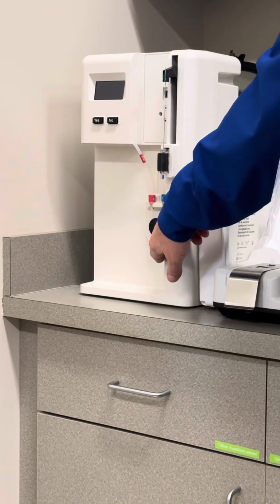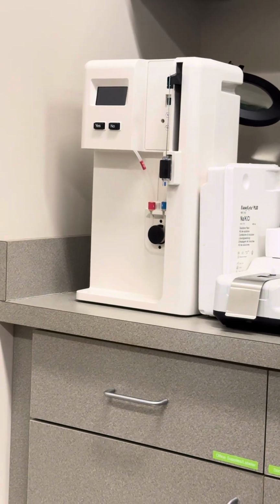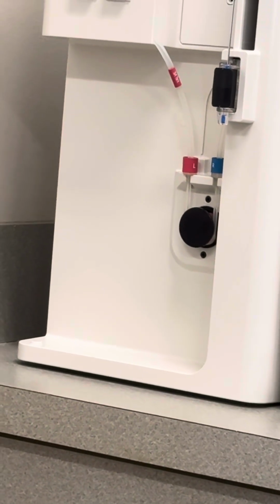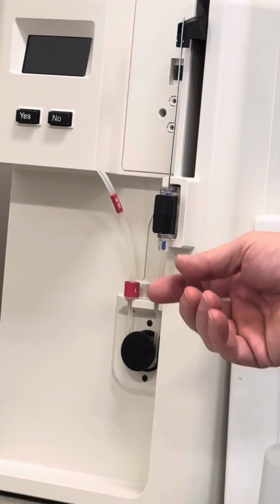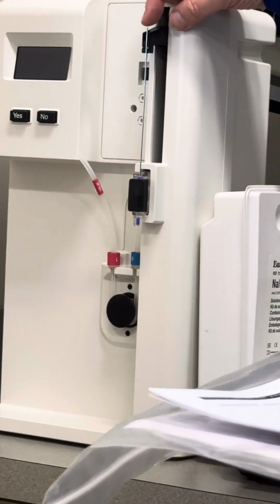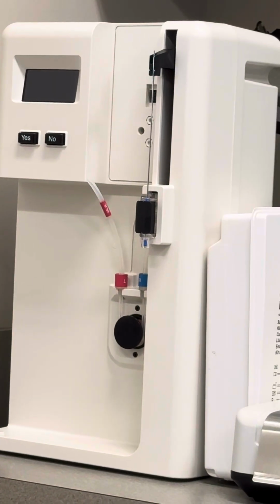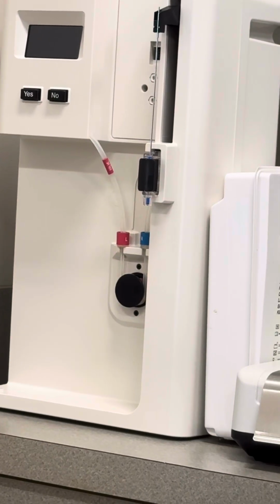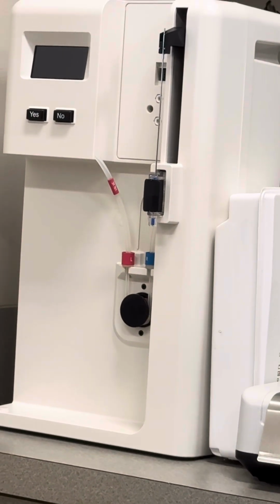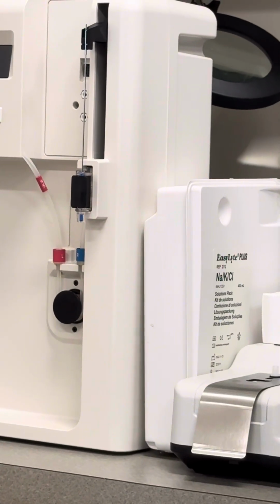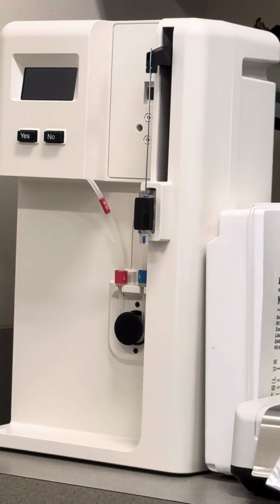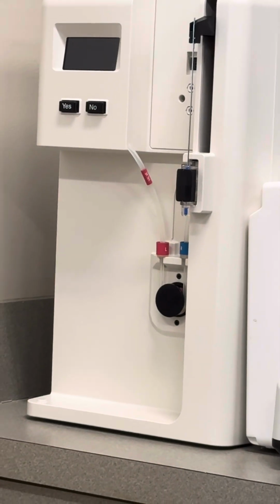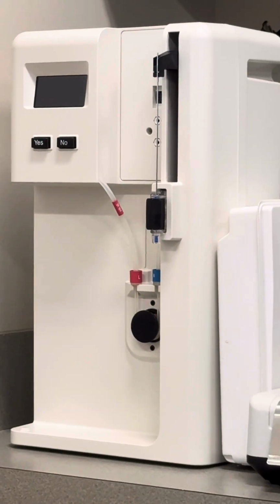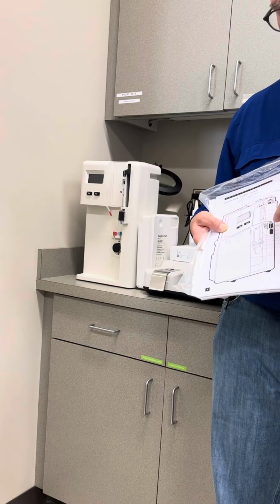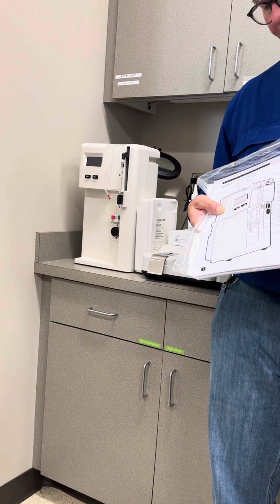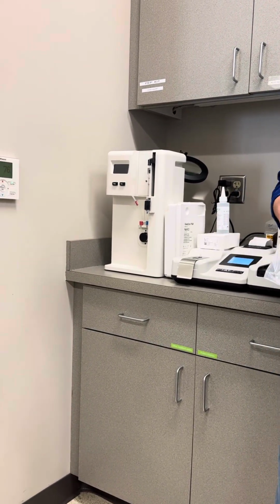Of course, you have your peristaltic pump and the tubing for it. It's right here. Then you have your sampling probe. And then your sampling tube will run from the top of your probe to this, which is actually your sample detector on the top of it. Depending on which test you're running is the way that your electrodes are set up. So you're going to have the sample detector, the potassium and your sodium, and then chloride or lithium or whatever other one you're running. And then you have a reference portion down here with your membrane assembly attached to that. So basically with this one, we're just going to put on the sodium and potassium electrode.